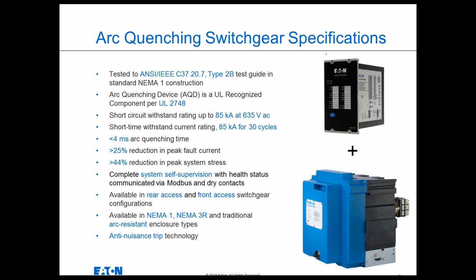But at a high level, as has been implied by my previous comments, the system consists of two main parts. The brains of the system is the Eaton arc flash relay, which looks for a flash of light from an arc flash and then uses that security signal of high current just to validate that it is an arc flash and not just somebody with a bright flashlight or a sunbeam or something like that. So that's the brains of the system. So not a lot of innovation here. As Chris said, arc detection systems have been around for a long time. The real innovation here was just figuring out how to eliminate that risk of nuisance operation. So the arc flash relay is the brains of the system. Then the arc quenching device is the heart of the system.